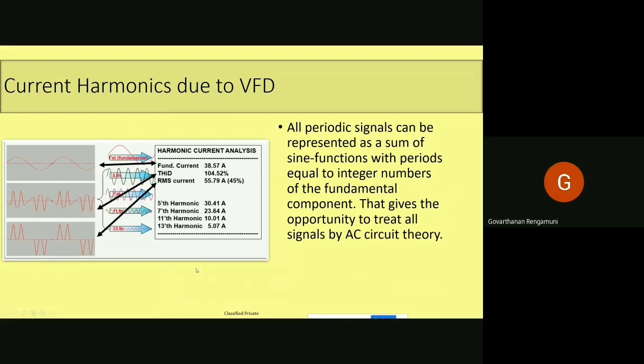Here, the current harmonics for a typical variable frequency drive without any harmonic mitigation is shown. The first waveform you are seeing is the fundamental current, and the last waveform is the actual current at the three-phase rectifier's input.